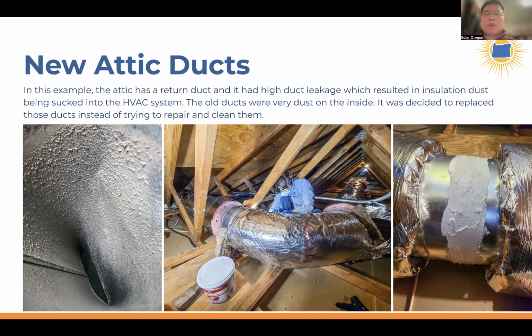The other thing that was found in this attic is that the ducts were also partially crushed from subsequent trades having to straddle and acrobat up and around and over this return duct, and sometimes unsuccessfully. So the duct was partially crushed. When the duct was replaced, the choice was made to install commercial grade spiral ducts. These ducts are much more heavy duty and rigid, so that if a trade in the future had to go in the attic and they bump into this duct or even accidentally lose their balance and sit on it, it would not necessarily crush.